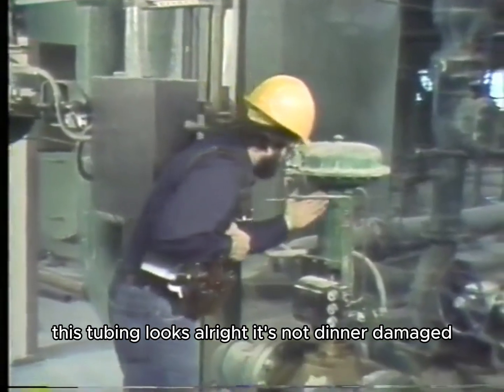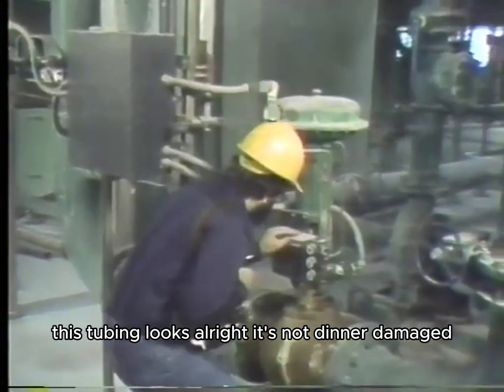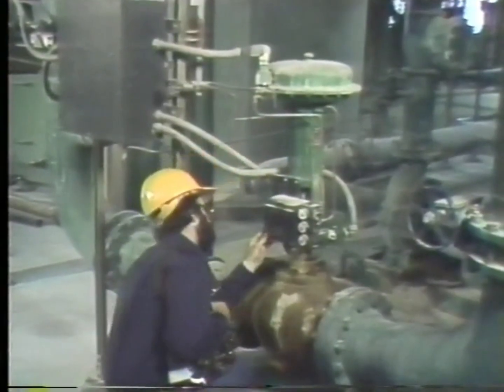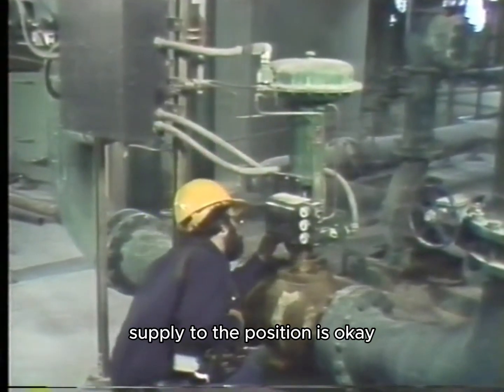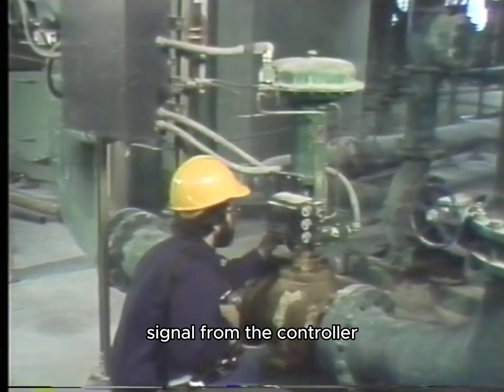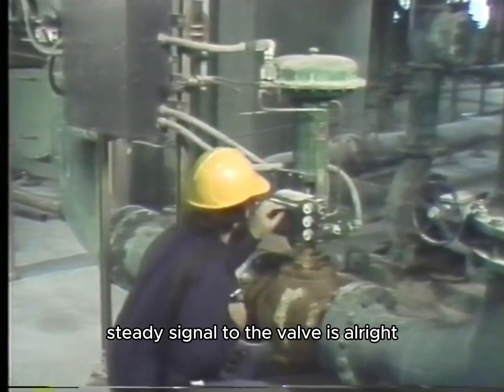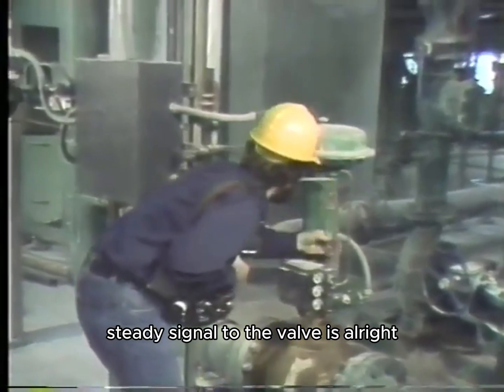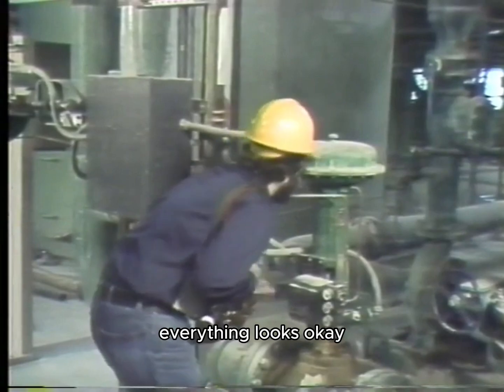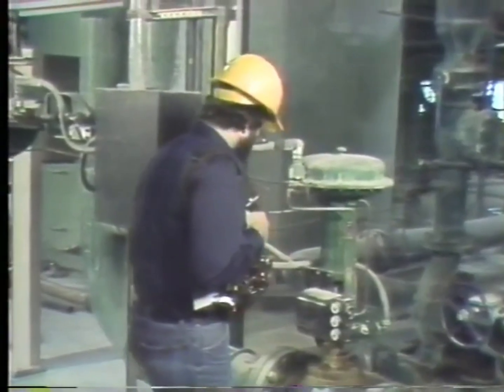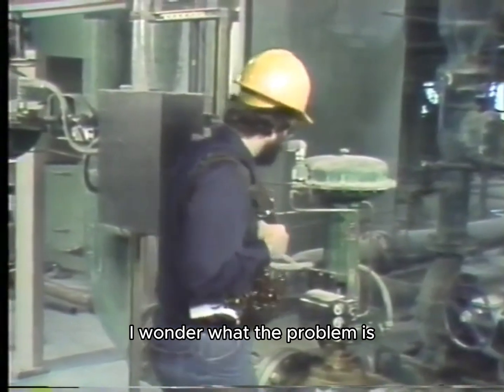This tubing looks alright. It's not bent or damaged. Supply to the positioner is okay. Signal from the controller is steady. The signal to the valve is alright. Everything looks okay. I wonder what the problem is.